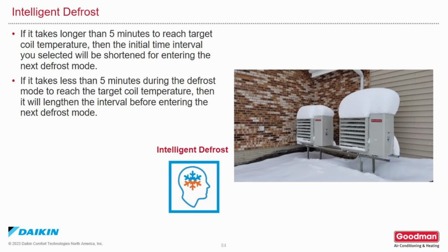Here's how intelligent defrost works. The best scenario is to keep the defrost cycle as short as possible. If it takes longer than 5 minutes to reach the target coil temperature, then the interval time that you selected will be shortened for entering the next defrost mode. If it takes less than 5 minutes during the defrost mode to reach target coil temperature, then it will lengthen the interval before entering the next defrost mode.